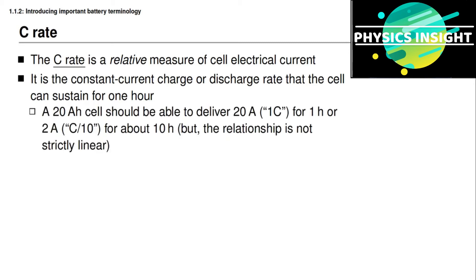For example, a cell having a capacity of 20 ampere-hours should be able to deliver 20 amperes for one hour, or 2 amperes for 10 hours. This relationship is not completely linear but is a good approximation. When we say the cell delivers 20 amperes for one hour, we are saying the C-rate of a 20 ampere-hour cell is 20 amperes — that is the 1C rate. The 2-ampere rate would be called the C/10 rate because it is one-tenth of the 1C rate.